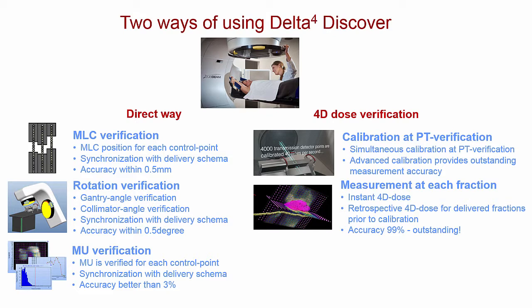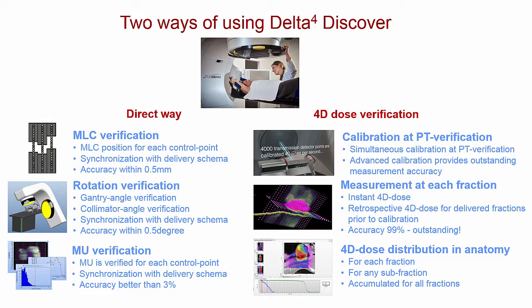So if you've done the direct way for a number of fractions, when you calibrate your device, you can get the 4D dose data for also the fractions prior to the calibration. The accuracy is outstanding. It's better than 99%, so it's really, really good. The data can now also be calculated together with CT or cone beam CT data to give you the dose distribution in anatomy.